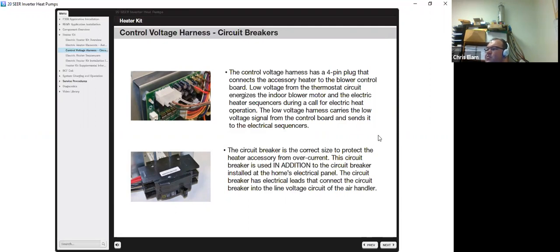The circuit breaker is the correct size to protect the heater accessory from overcurrent. This circuit breaker is in addition to the circuit breaker at the home panel. The circuit breaker has electrical leads that connect to the circuit breaker and to line voltage. So you basically have two breakers on each circuit. If you have a short in the furnace itself, chances are, in theory, this breaker here should trip first. If your breaker at the panel is tripping, chances are you may have a bad breaker in the panel or a loose connection at the panel.